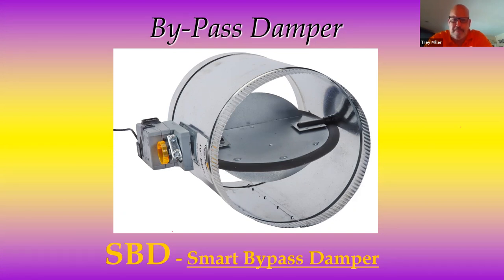Therefore, this smart bypass damper has a built-in digital manometer. With a push of a button, we can capture the design static and maintain it, whether I'm in first stage, second stage, heating, cooling, any zone combination. So gentlemen, the opportunity here is, in retrofit especially, if you have a duct system that's in good shape, you put this in, if I maintain design static, the unit doesn't even know it has zoning on it. Therefore, we dehumidify, we run with the same efficiency, we increase latent cooling effect, we reduce temperature in cooling, increase temperatures in heating, and I'll explain that as we go through the system.